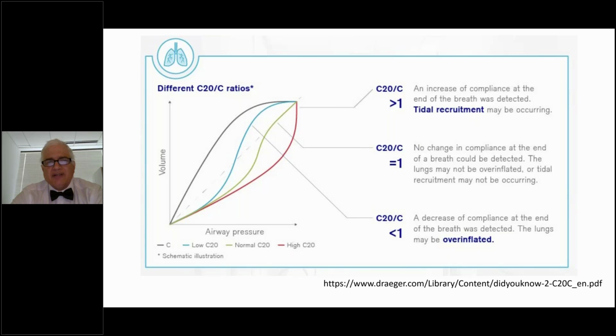Now, when you start to see issues is when there is a problem with this inspiratory limb. And what tends to happen is that you see this limb buckling in on itself somewhat. And it tends to match the line of identity, which is the line of dynamic compliance, which is reflected in here as this dotted line. So as this inspiratory compliance limb tends to approximate to that limb, what happens is that your C20C starts to approach 1. What does that mean? What it means is that the last 20% of this loop as compared to this whole dynamic compliance here is basically the same. You're starting to get to the point where you're going to be in trouble.